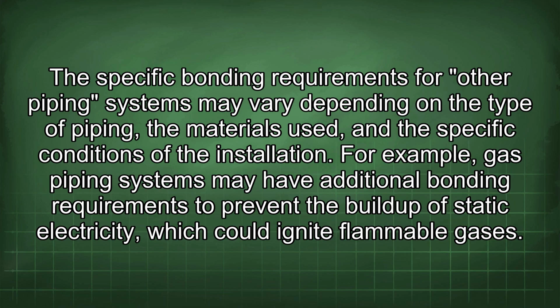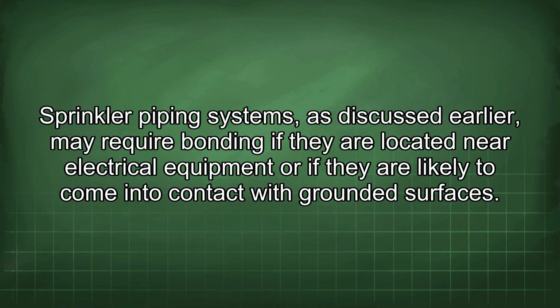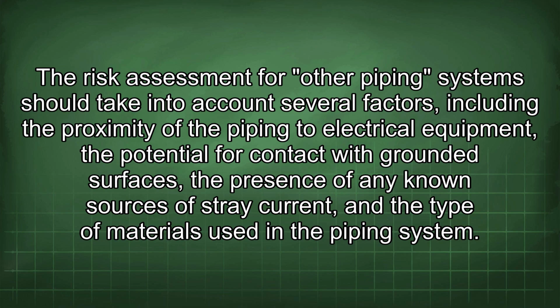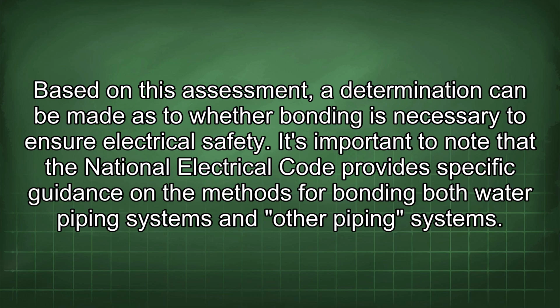For example, gas piping systems may have additional bonding requirements to prevent the buildup of static electricity, which could ignite flammable gases. Sprinkler piping systems, as discussed earlier, may require bonding if they are located near electrical equipment or if they are likely to come into contact with grounded surfaces. The risk assessment for other piping systems should take into account several factors, including the proximity of the piping to electrical equipment, the potential for contact with grounded surfaces, the presence of any known sources of stray current, and the type of materials used in the piping system. Based on this assessment, a determination can be made as to whether bonding is necessary to ensure electrical safety.